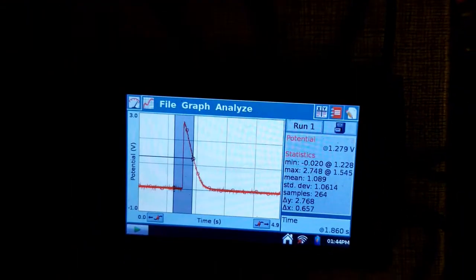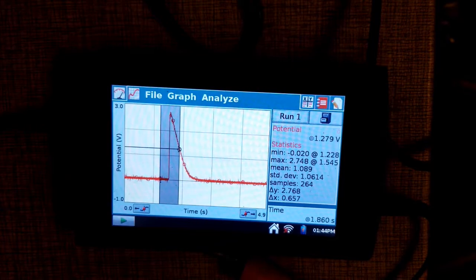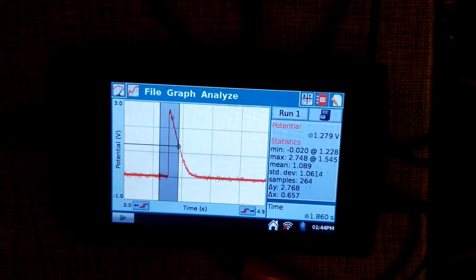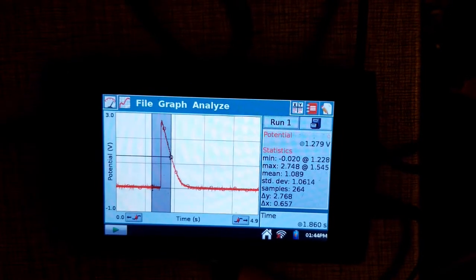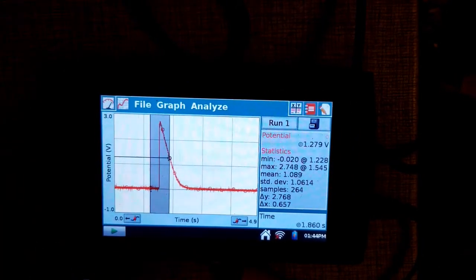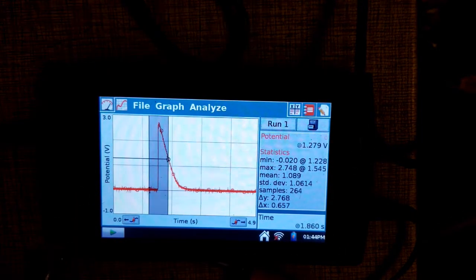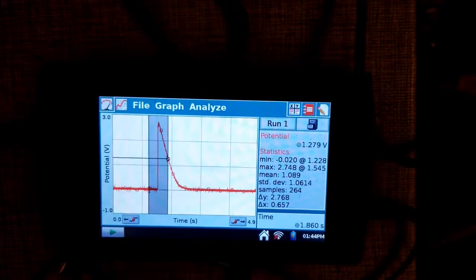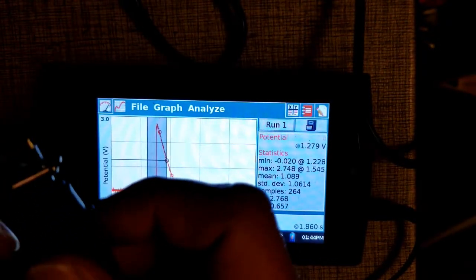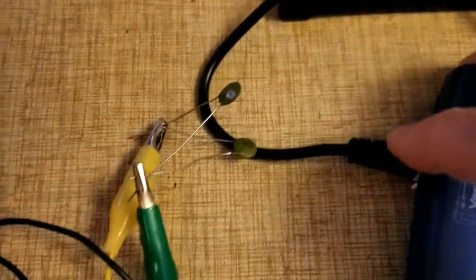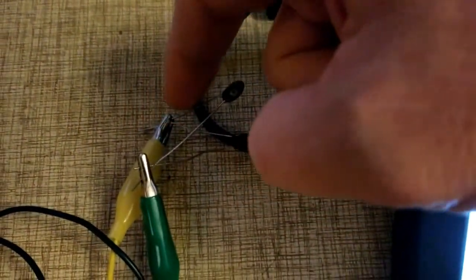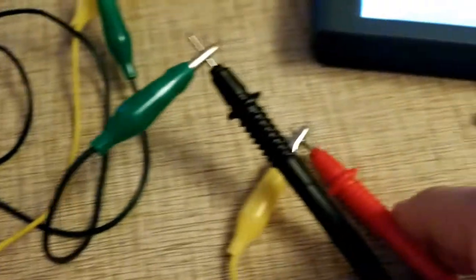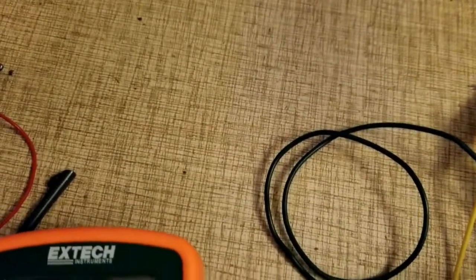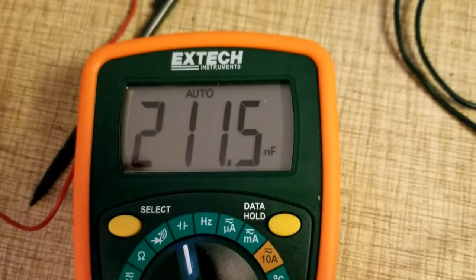So actually, first thing, before we turn on the current, I do need to find the equivalent capacitance, and I need to do that while it's not connected to the power supply. So we'll bring the meter back. One side hooked to that probe, and the other side hooked to that probe. Oh, that's a lot of backlighting. All right. So I now have yellow hooked to one side, green hooked to the other. Yellow and green are hooked to my 2 probes here. We need to put this on capacitor, and so we get the equivalent capacitance.